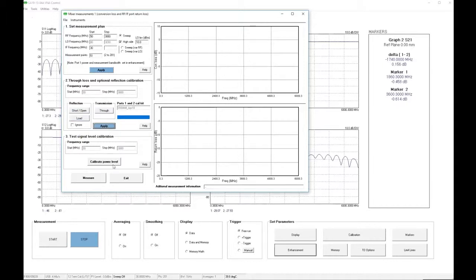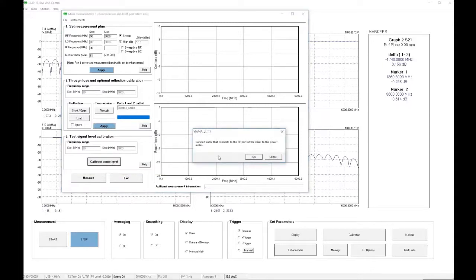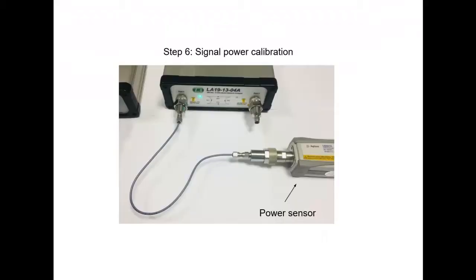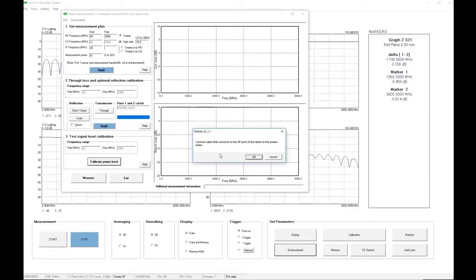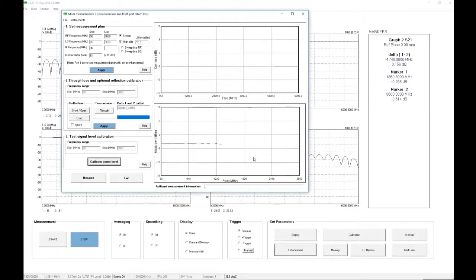We now do the final step of the calibration, and that is to use the power sensor to calibrate the power level from port 1 of the VNA. Okay, once we have the power sensor connected, we are ready to go. Here is how we need to connect the power sensor to the end of the cable from port 1. We then click OK to make the measurement. And there we are, we have done the calibration.